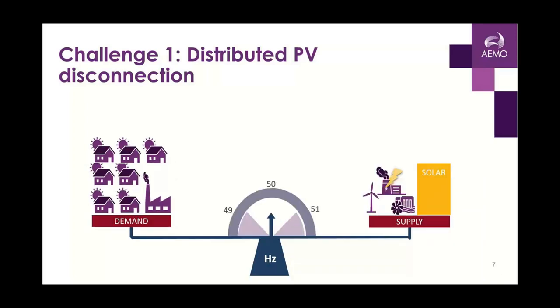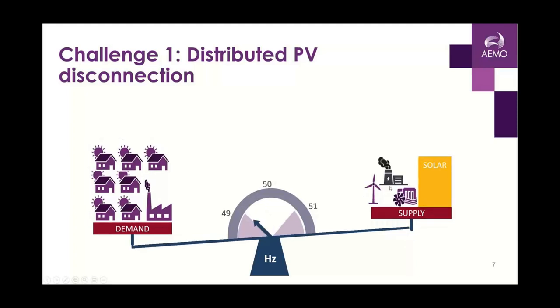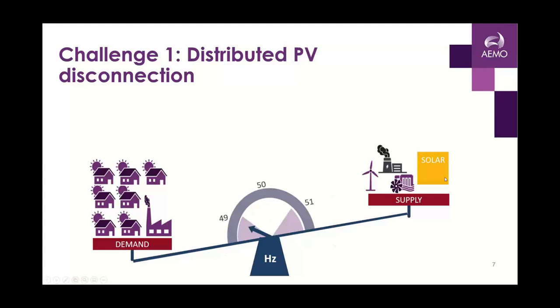What we've found, though, is that sometimes the behavior of solar is actually not helpful in some situations. Once again, we have this supply-demand balance, our solar is on the right side, and then we might have an incident. For example, we might see a fire at a generating station like a coal plant, which we can't necessarily predict, and then suddenly we see a trip of that system. So the balance is out. And what we've been seeing is that, as a consequence of that trip, solar's response is to also disconnect, which means we put ourselves in a position where our supply-demand balance is even further out of whack, rather than being in a position where we are able to correct for it.